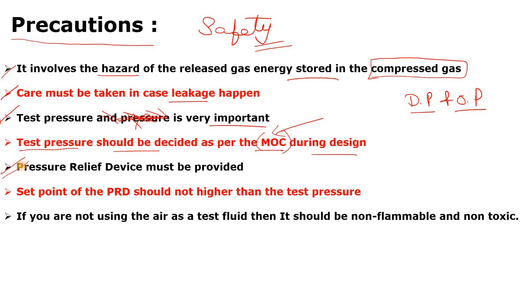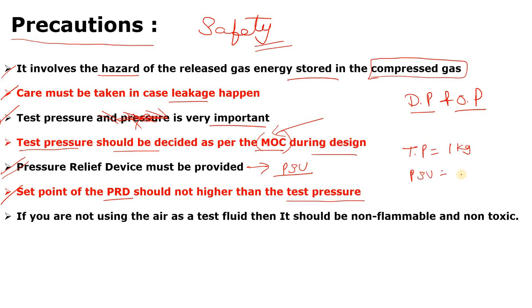Pressure relief devices must be present because you are injecting air to pressurize the loop, and in case of over-pressurization, it may rupture the pipeline or vessel. That is why a PRD must be there — if there is over-pressurization, the PSV can pop up to protect your system. The set point of the PRD should not be higher than the test pressure. For example, if test pressure is 1 kg/cm², your PSV set point at 2 kg/cm² makes no sense — it must be within the range.